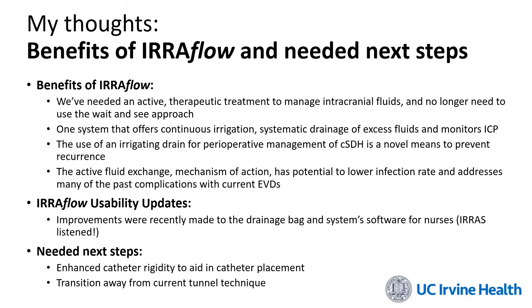During the time we tested the IRRAflow system, IRRAS was very forthcoming in making improvements. They improved the drainage bag as well as the software so that nurses were better able to use the system and we were better at understanding the data coming out of it. In the future, the two main things that need to be addressed are catheter rigidity — to ensure that when placed into the ventricle or subdural space it doesn't kink off and stop drainage or irrigation — and a new tunneling technique, since the current system is not ideal for placing the drain subgaleally and in the subdural space.